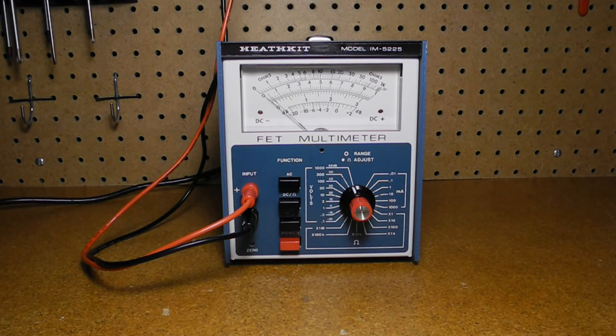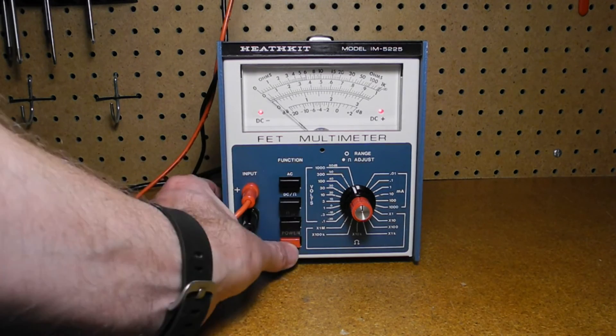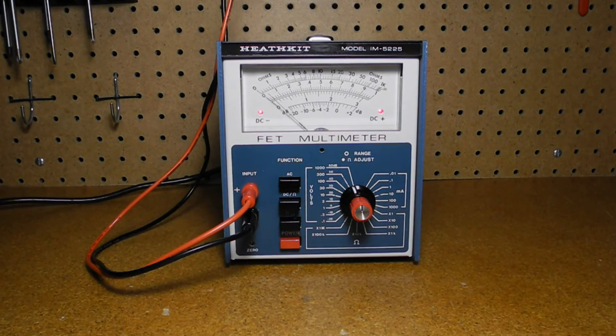The operation is pretty straight forward. The test leads connect to the plus and minus inputs. Turn the unit on using the power switch. Press the AC button to measure AC voltage or current or DC ohms to measure DC voltage or current or resistance. Press ohms low voltage to measure resistance using the low test voltage.